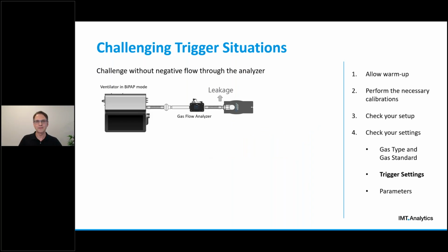So we've learned that the default trigger settings work well in most applications as long as you have a positive and negative flow through the gas flow analyzer, and that these trigger settings are then independent from your ventilator settings. So the bad news is that this is not always the case, and that might explain why some of you had to touch the trigger settings. So let's have a look at such a situation as an example where it gets a little bit more challenging to find suitable trigger settings.